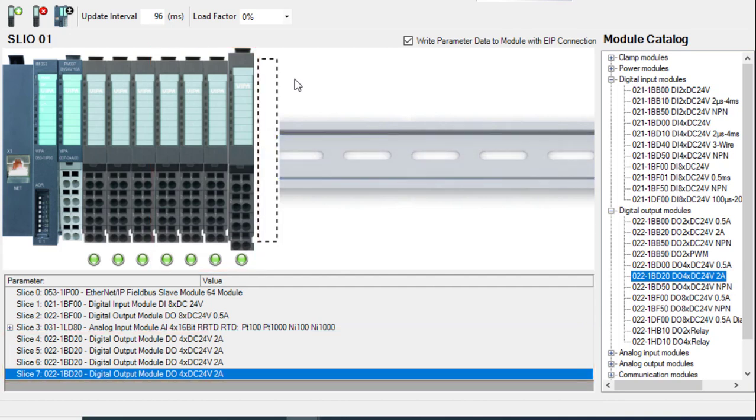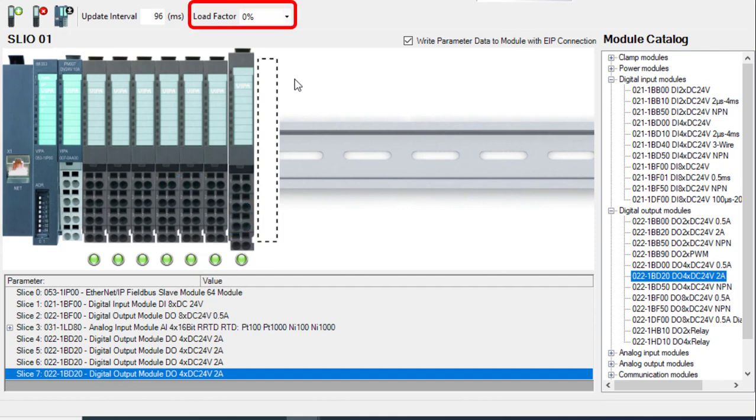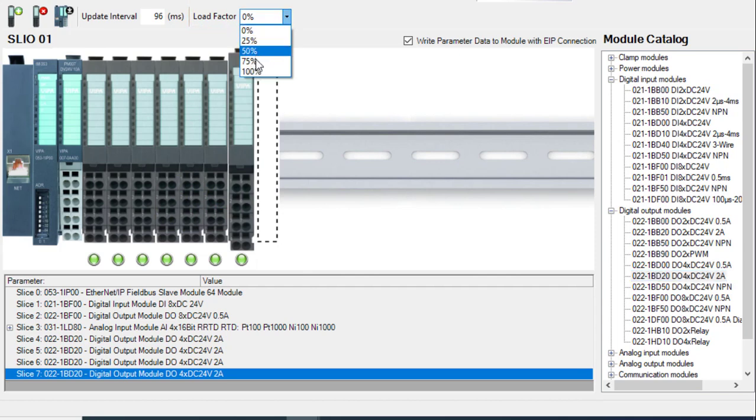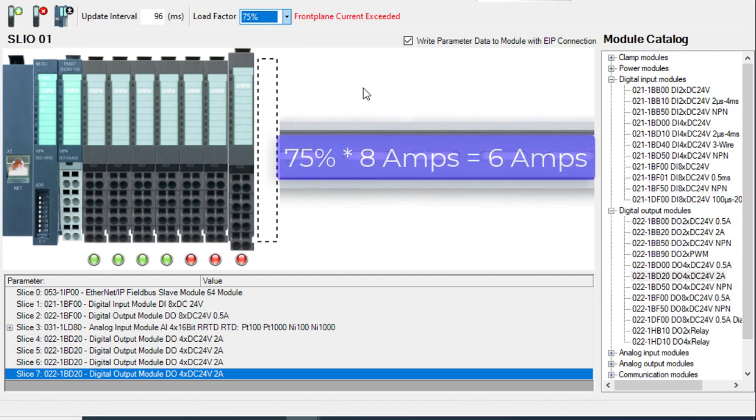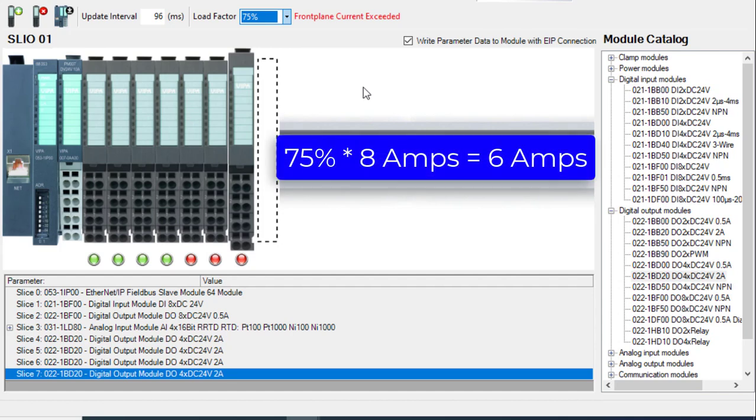But the actual power consumed depends on the connected load and the number of outputs connected. We can use the load factor to estimate this power. For example, 75% means each slice uses 75% of the max current. The output slices would use 6 amps, not the full 8 amps.